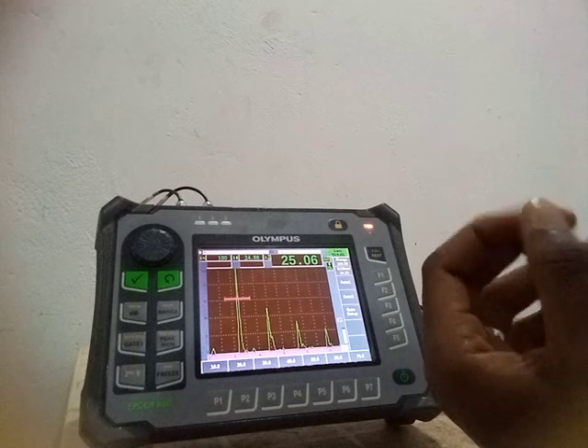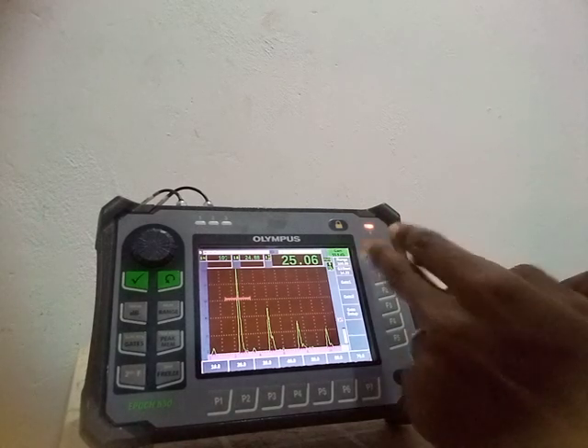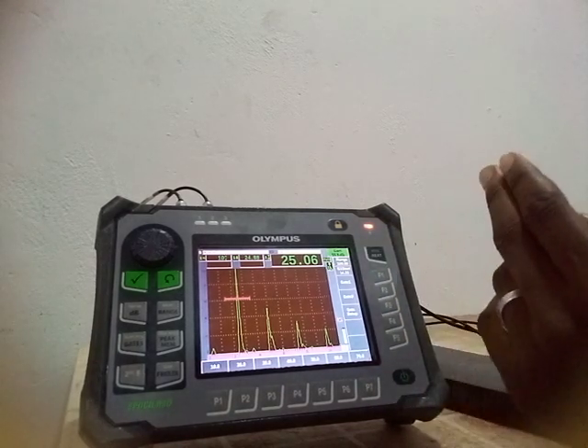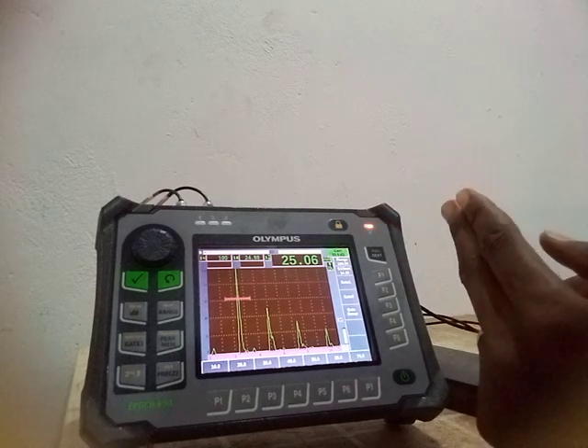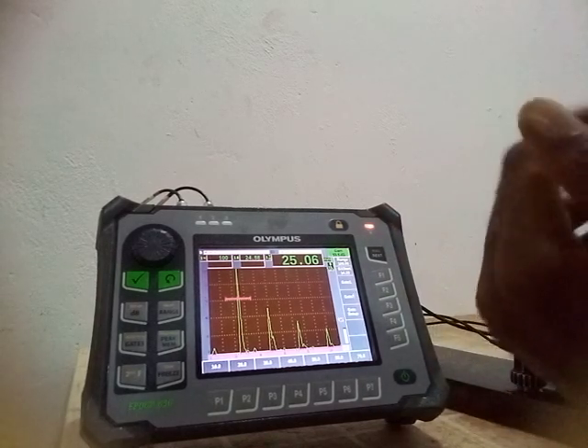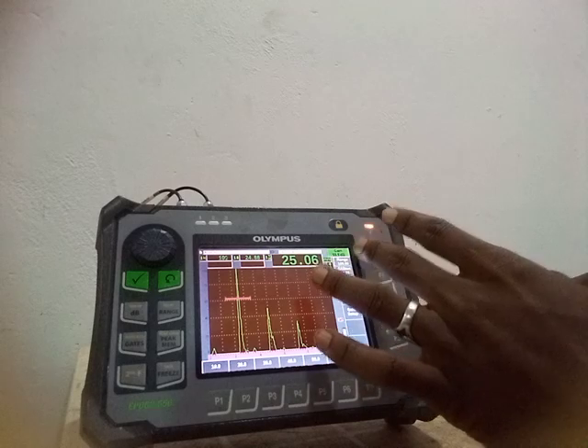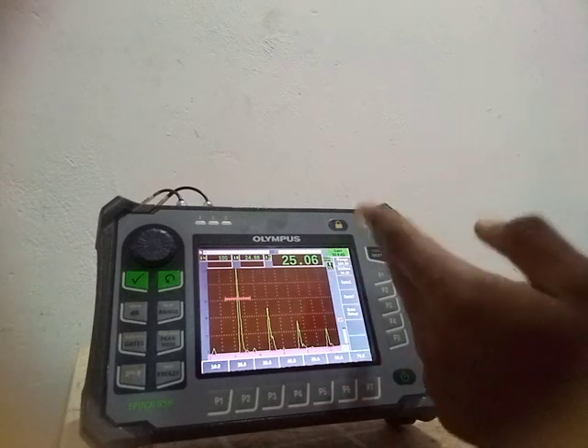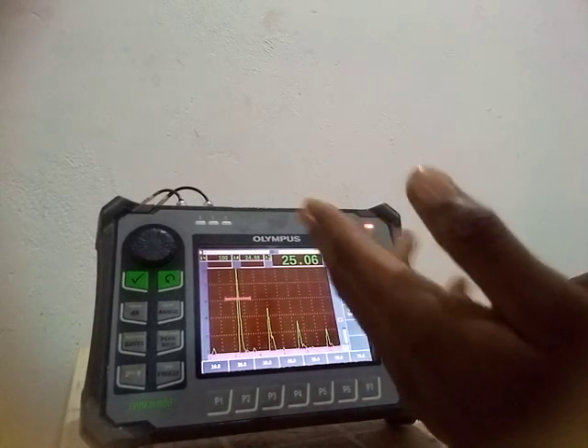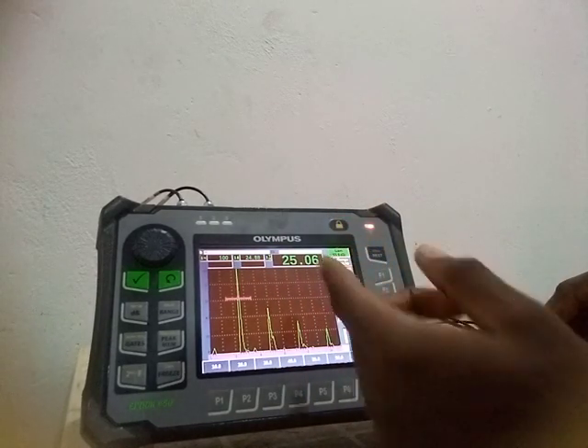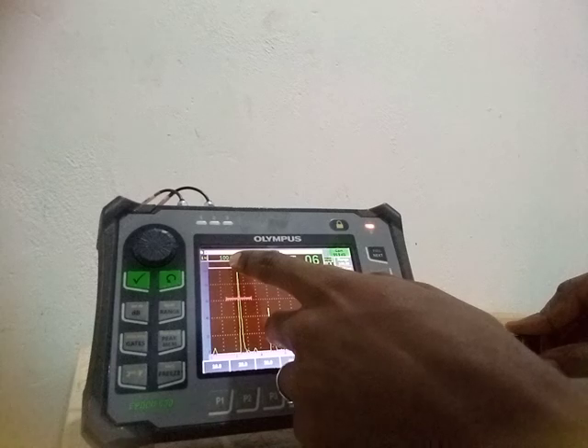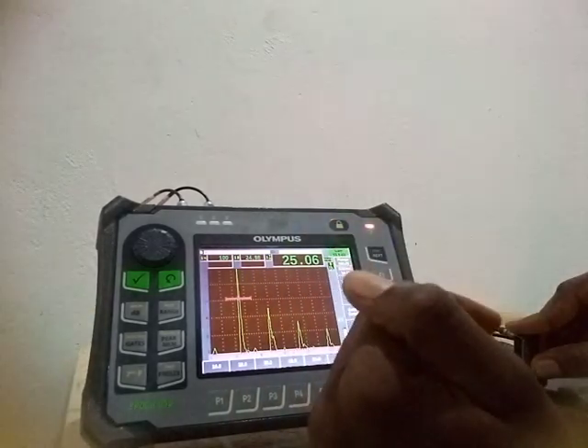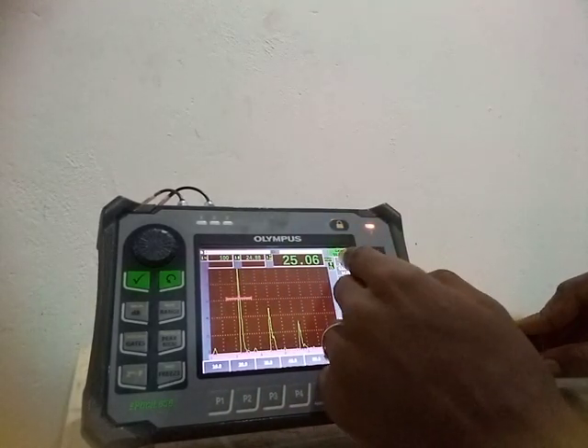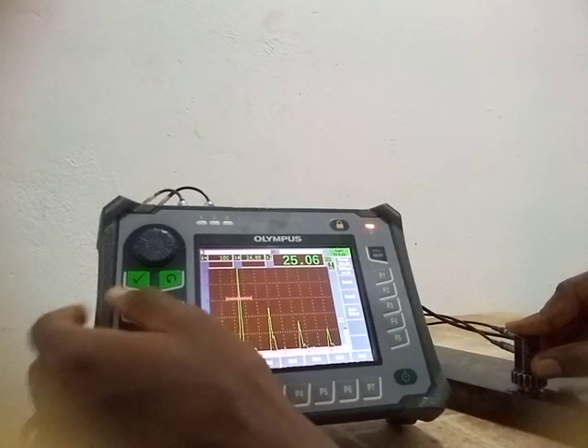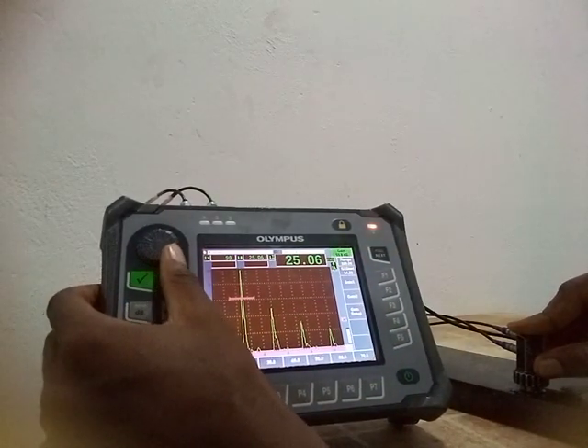Since we now know that before it was 53.9, we added 2, making it 55.9. Depending on what gain you got, you add 2 to it, and you get 101. So now let's reduce 2 from this gain, and we're expecting our amplitude percentage to come back to 80. Now we're having 55.9. Let's reduce to 53.9.